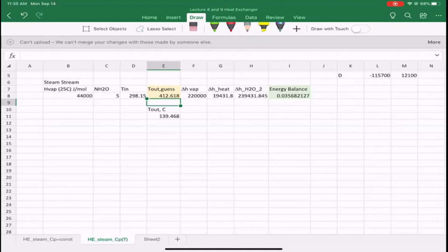Now, how you would respond to that in the real world is very simple. You would just meter more water into the system. Feeding liquid water into a heat exchanger and slightly increasing the amount of water is a relatively straightforward thing to do. But then again, what if you had to buy a pump to do this? To get the flow rate high enough that the exhaust temperature is acceptable, we had to increase the flow rate by about 40%.